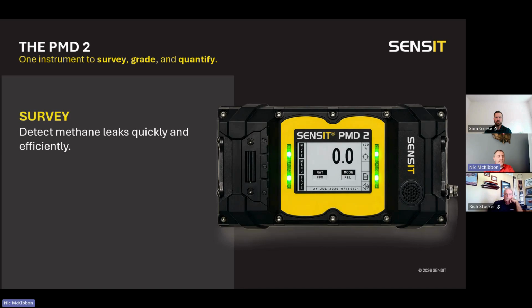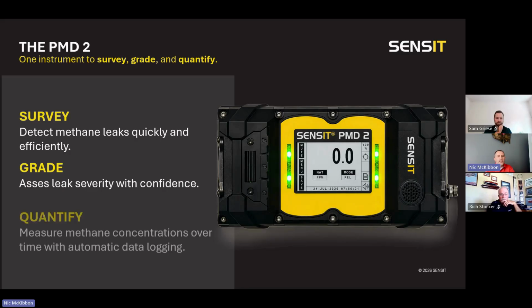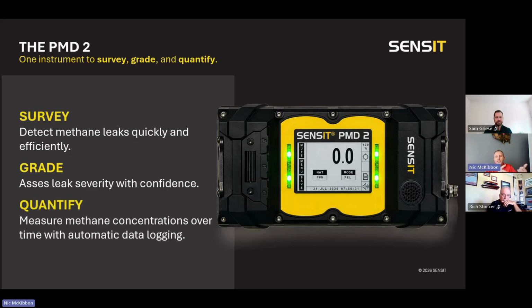Just like the slide says, it's one instrument to survey, grade, and quantify a gas leak. Based on a gas leak's location, the hazard potential, and the readings, it gives you a tool as an operator to take the appropriate safety actions and set repair priorities.